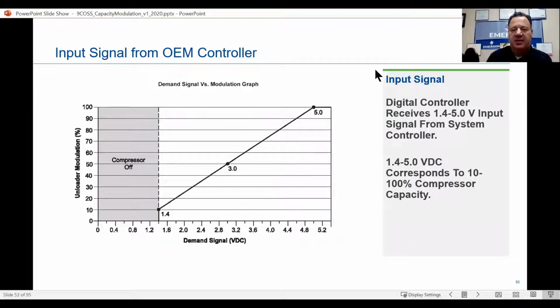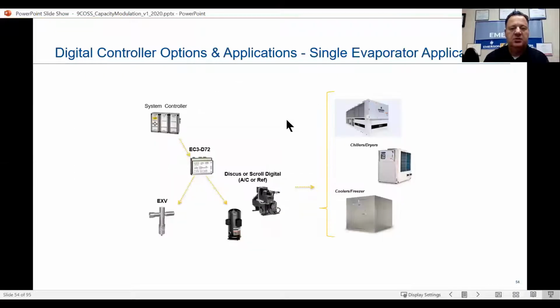Okay, 10% is the equivalent of 1.4 volts. So at 100%, we're at 5 volts, okay? You can see the unloader modulation percentage-wise over here. So at 10%, again, it's the equivalent of 1.4 signal volts on the demand on DC. At 50% would be 3 volts DC. Input signal: the digital controller receives a 1.4 through 5 volts input signal from the system controller, and it corresponds to 10% to 100% compressor capacity. Digital controller options and applications, single evaporator application.